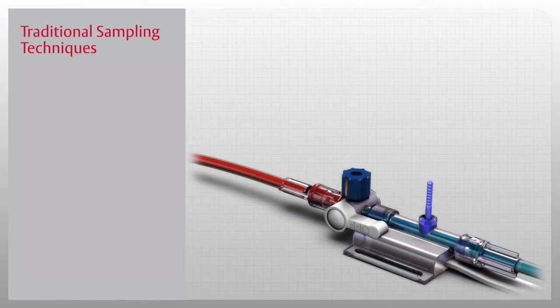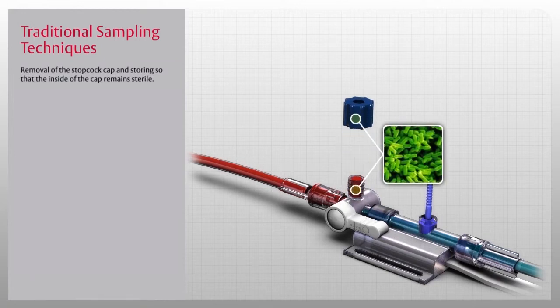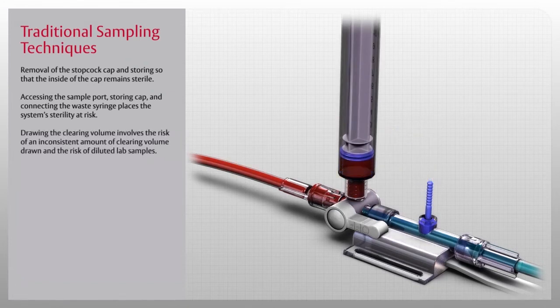The Edwards VAMP family of closed blood sampling systems is designed to protect the patient and the clinician from complications associated with traditional sampling techniques. Traditional sampling risks in the critical care setting involve removal of the stopcock cap and storing it so that the inside of the cap remains sterile. Accessing the sample port, storing the cap, and connecting the waste syringe places the system's sterility at risk. Drawing the clearing volume involves the risk of an inconsistent amount of clearing volume drawn and the risk of diluted lab samples.